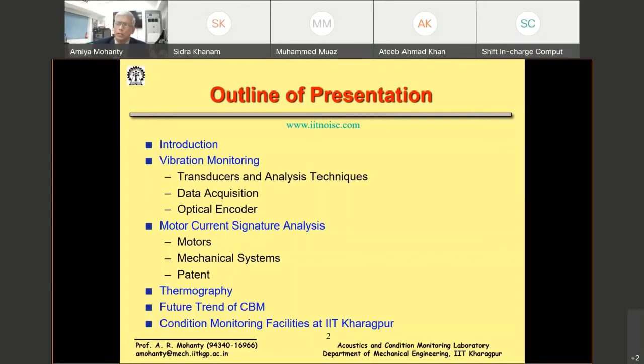We looked into the literature, and somewhere in 1974 at the Oak Ridge National Laboratory in the US, in the nuclear reactors, when they were opening servo controlled valves, there is a reference that they measured the motor current of the servo motor, and they could realize if the valve closed or opened by looking at it. Obviously we could not patent it because it was not our idea, but we took it further. I will come to that story later on.